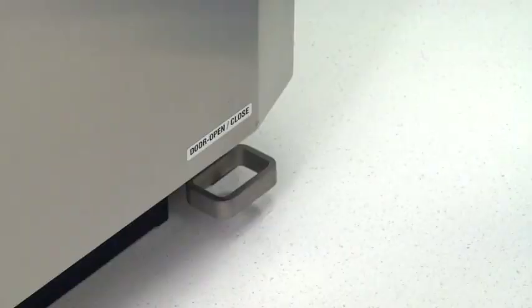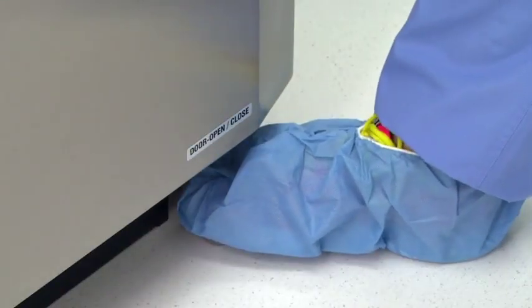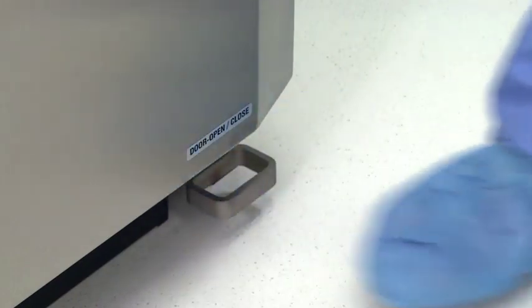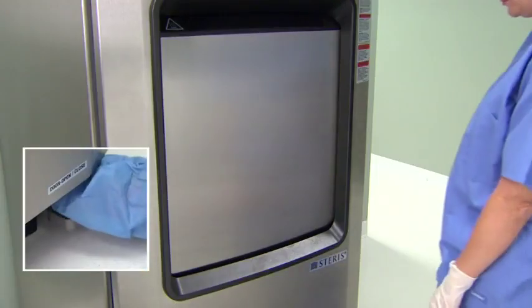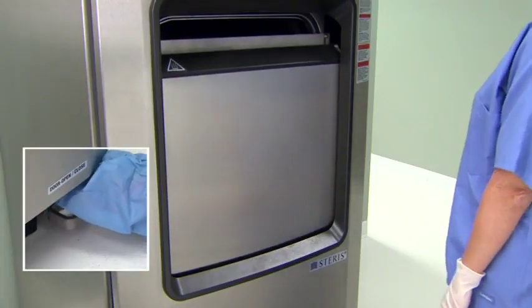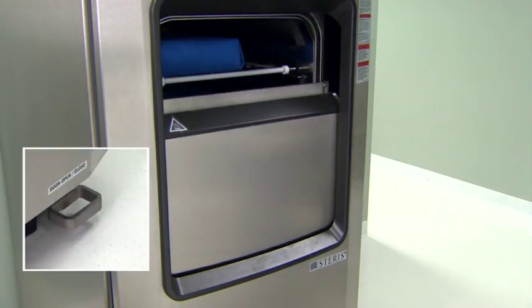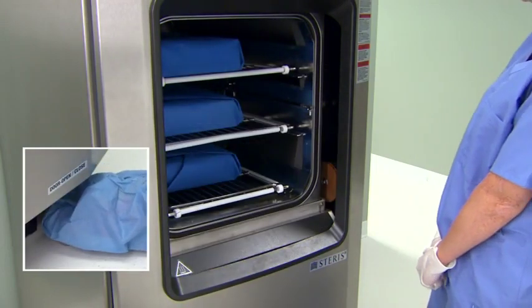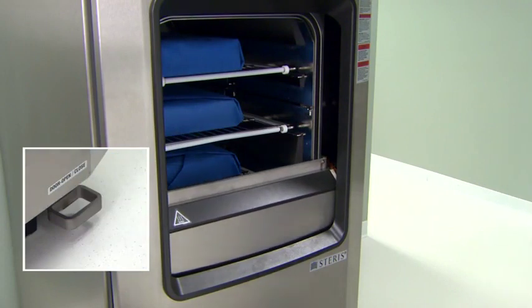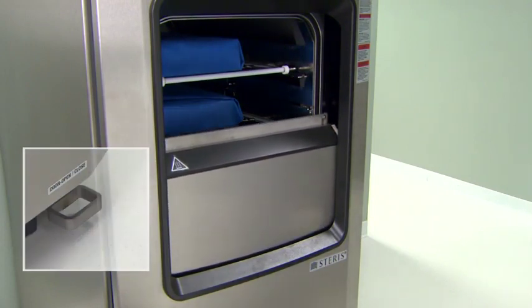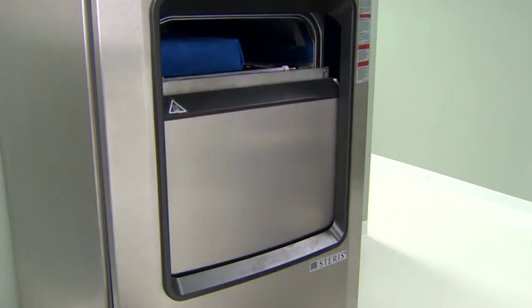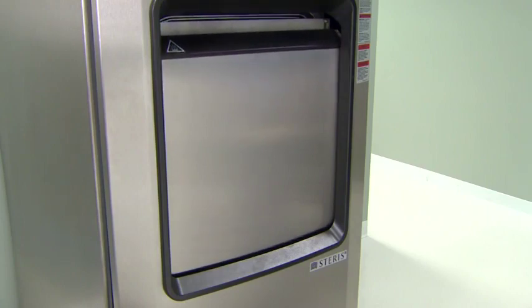The AMSCO 400 series sterilizer is equipped with a foot pedal that opens and closes the sterilizer door. Pressing the foot pedal while the door is in the closed or up position causes the door to open. Pressing the foot pedal while the door is in the open or lowered position causes the door to close. Keep the door closed when the unit is not in use.